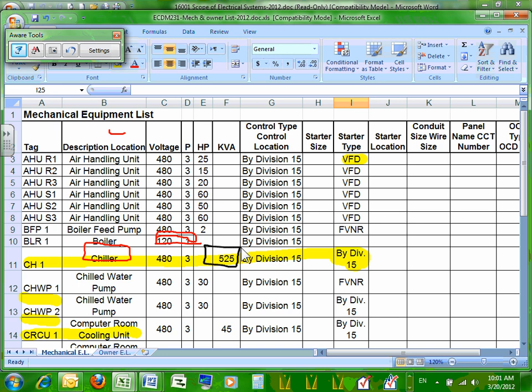You either put motor or not, column B or column C, and I don't care which one it is, because I know which one is appropriate to the task. Some chillers have some peripheral things hanging on, but the motor is probably 95% or greater of the load.